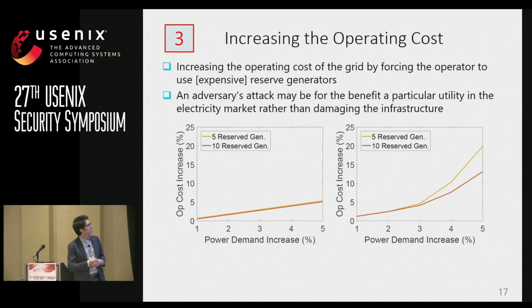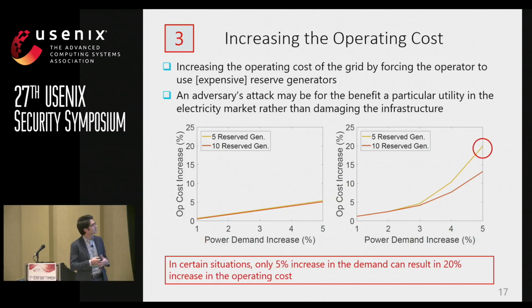And finally, as I said earlier, if the attack doesn't result in any damage to the grid, it can result in an increase in the operation cost of the grid, or the adversary's attack may be for the benefit of a particular player in the electricity market rather than damaging the infrastructure network. We did several simulations, but to cut the story short, we observed that in some situations, only a 5% increase in the demand can result in a 20% increase in the operating costs, which is a significant amount.